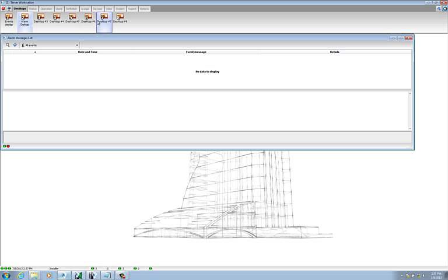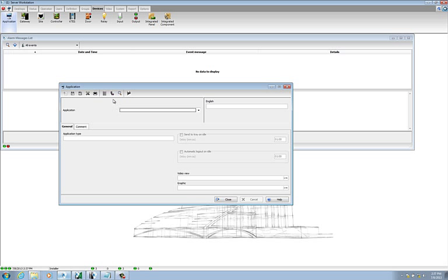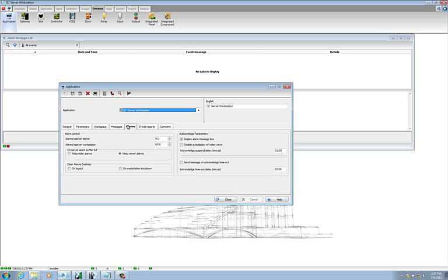The fifth thing we have to do is to go under devices, then EntraPass application, and select the server workstation. From there, if we go under the alarm tab, those are the parameters for the pop-up. The checkbox is set to display the alarm, so when the alarm comes on, a pop-up is going to come up. Also the acknowledgement suspend delay is 1 minute.